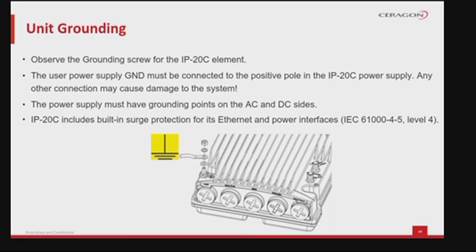4. The second side of the grounding cable should be connected to the main ground bar or terminal ground bar of the site. 5. Perform a resistance test between the two lugs of the grounding cable. Verify that the result is between 0 to 2 ohms. The unit's grounding screw terminal shall be permanently connected to protective earthing system in a building installation in accordance with applicable national code and regulations by a service person.